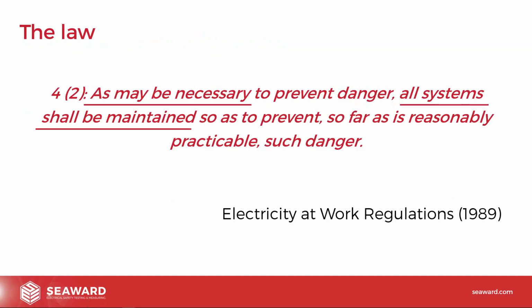So we talked about Regulation 4, Paragraph 2, the Electricity at Work Regulations 1989, and it's important to actually read this because, as we said, it doesn't mention PAT testing, but there are some important bits in here. So it says, as may be necessary to prevent danger, all systems shall be maintained so as to prevent, so far as is reasonably practicable, such danger. So there's a few things we need to be aware of in there really. The first one is how often do we need to do it?